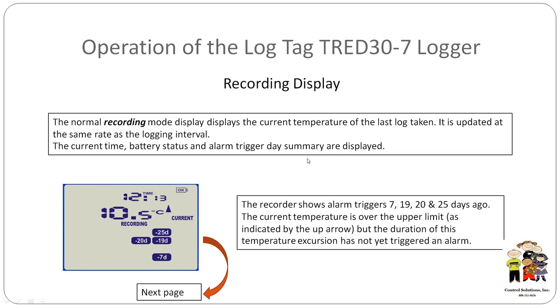Some of the data that you can display on your logger: the log tag has the ability to go back up to 30 days in history to let you know what the min-max was, and if there was any alarms, what was the amplitude of being too hot or too cold, and how long it was at that particular temperature. So if we came into our office on a Monday and we saw one of these days down here blacken, it's telling you that you had an alarm condition during that day.